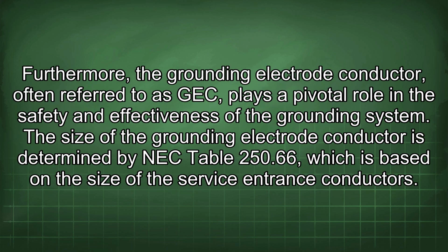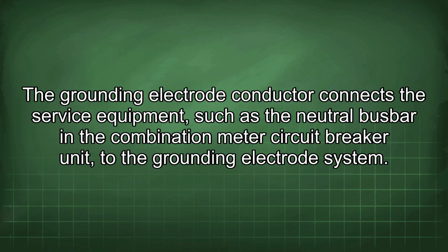Furthermore, the grounding electrode conductor, often referred to as GEC, plays a pivotal role in the safety and effectiveness of the grounding system. The size of the grounding electrode conductor is determined by NEC Table 250.66, which is based on the size of the service entrance conductors. The grounding electrode conductor connects the service equipment, such as the neutral busbar in the combination meter circuit breaker unit, to the grounding electrode system.